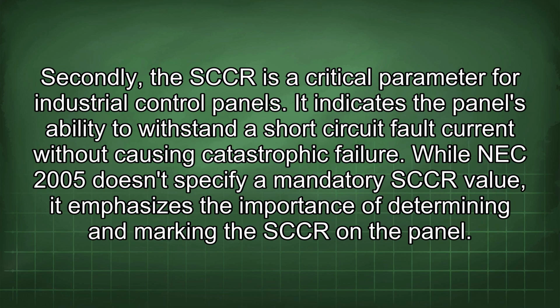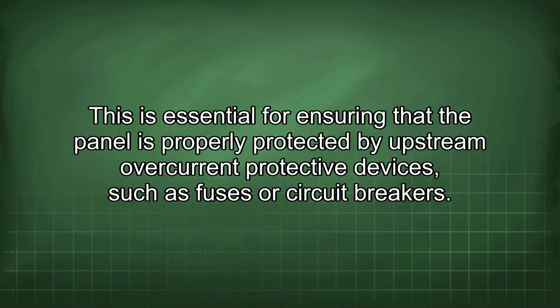Secondly, the SCCR is a critical parameter for industrial control panels. It indicates the panel's ability to withstand a short-circuit fault current without causing catastrophic failure. While NEC 2005 doesn't specify a mandatory SCCR value, it emphasizes the importance of determining and marking the SCCR on the panel. This is essential for ensuring that the panel is properly protected by upstream overcurrent protective devices such as fuses or circuit breakers.